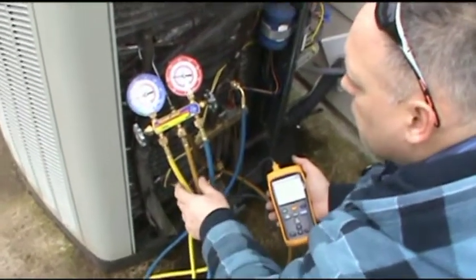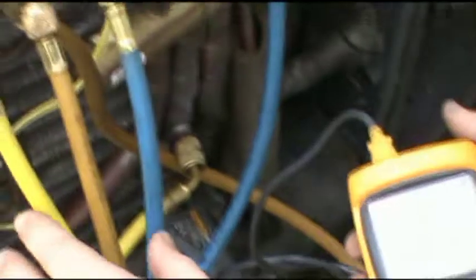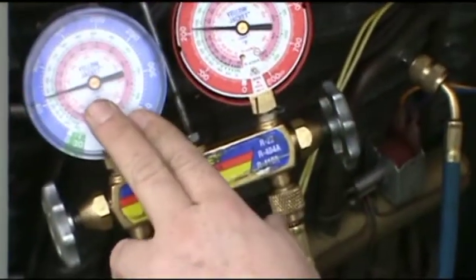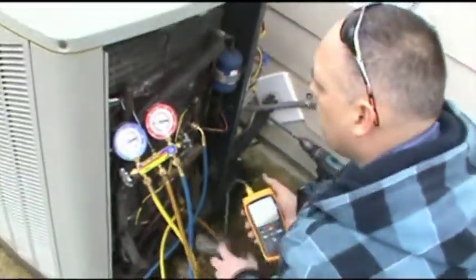About right. We want to see about 20 or so degrees warmer than our saturated suction temperature, which if you look at my gauge is approximately 33 degrees. So we're 18 degrees difference. So that's about right. That's where that number should be.